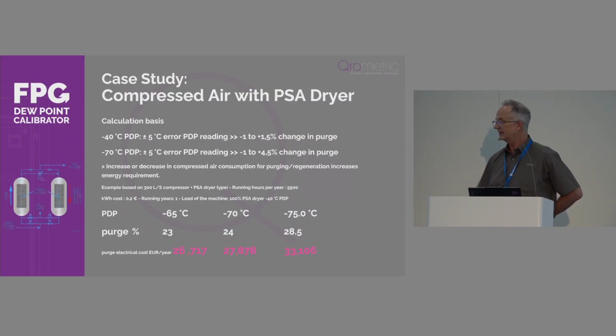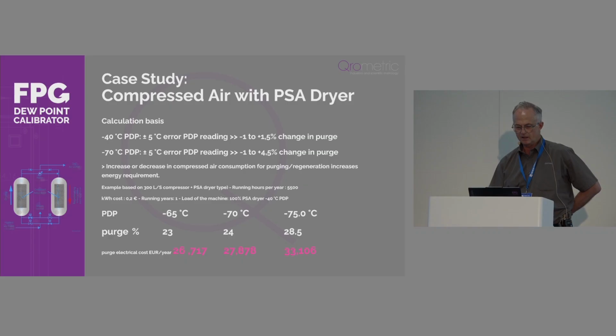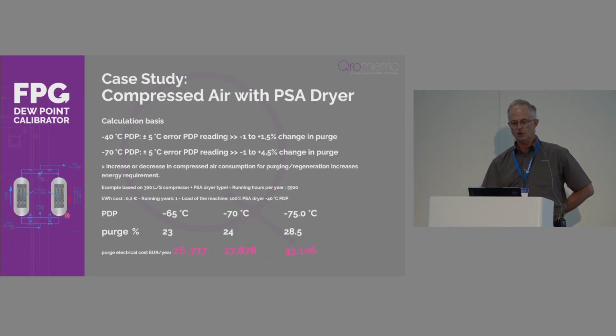Now here's a case study which was provided with some help from a compressor manufacturer. Here we have an example of the cost of running a compressed air drying system. With a typical PSA dryer, pressure swing adsorption dryer, you have one drying column and a regeneration column. And this column is then used to dry the gas that's coming out of the system.